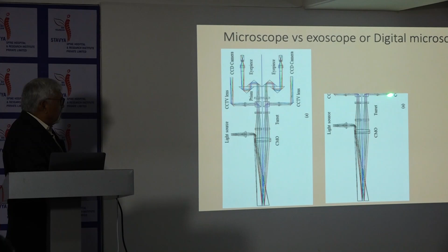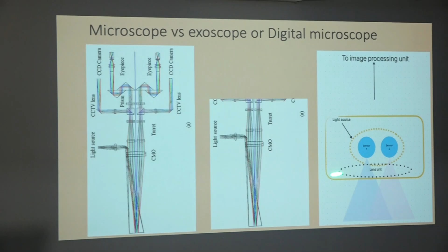Now this is the construction of the camera, but when you come to the exoscope, from here onwards there are two sensors which will directly receive the light, and whatever happens is happening at a digital manipulation level. Now that has advantages because the technology is superior compared to the technology we have where we see and perceive in the brain. Now this is what happens in an exoscope. Instead of light reaching the eyes, it will go to the sensors. From the sensors it's picked up, and then the processing unit will display it as two images superimposed on a screen. Now when you use the goggles, they fuse the image and give you a stereoscopic perception.